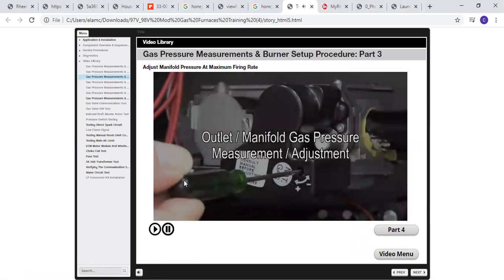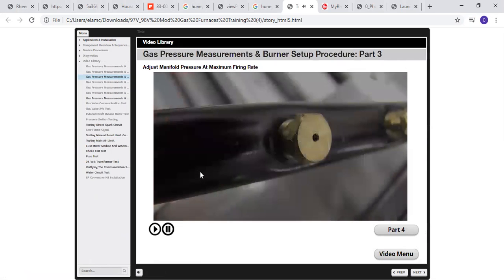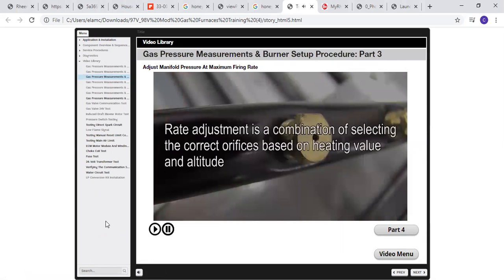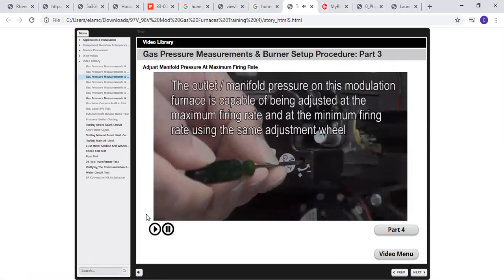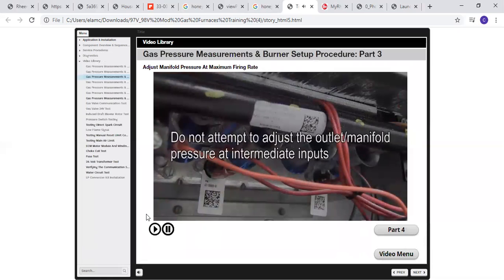Outlet manifold gas pressure measurement and adjustment. Rate adjustment is a combination of selecting the right orifice based on the heat value and altitude. The outlet manifold pressure on this modulating furnace is capable of being adjusted at the maximum firing rate and at the minimum firing rate using the same adjustment.